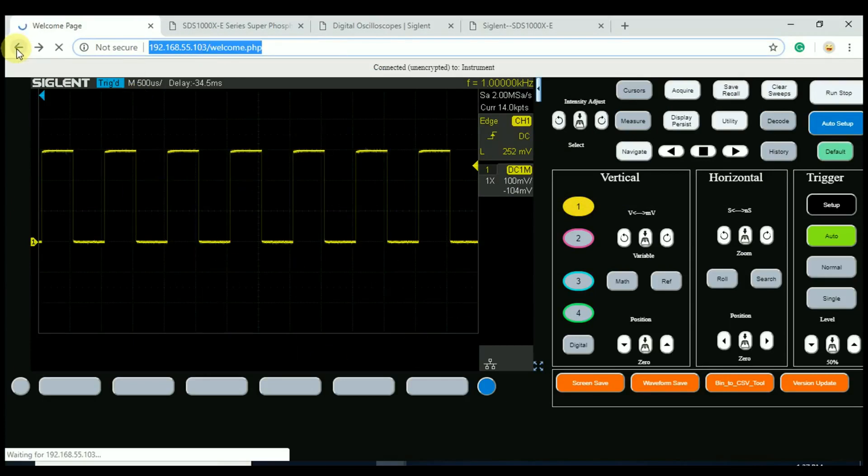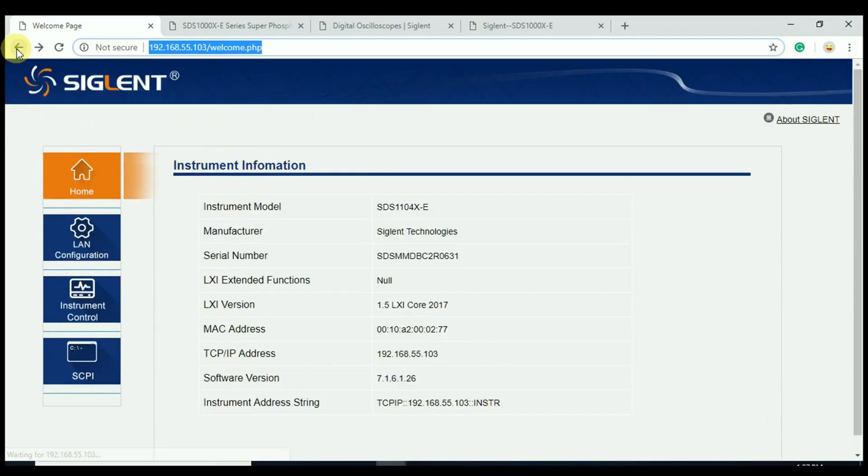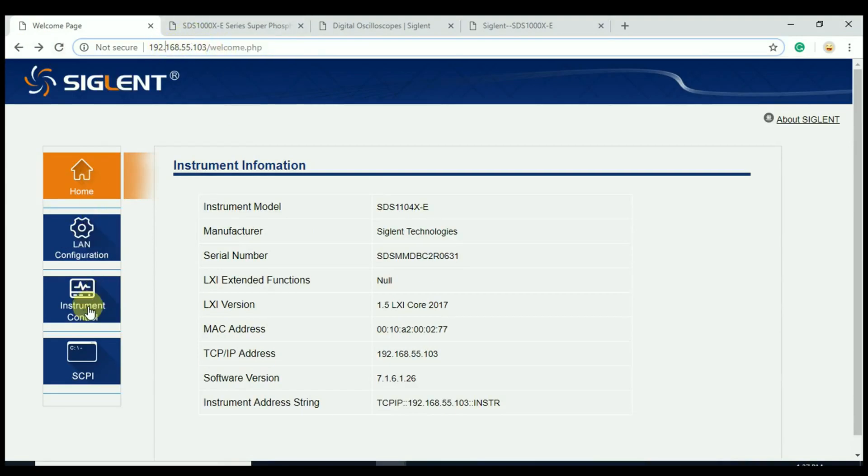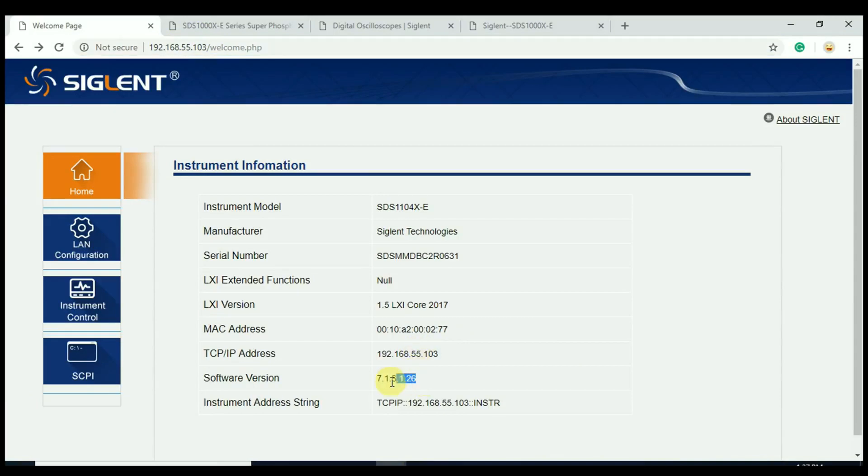So just go back arrow to the welcome page, type in the IP address up here, hit enter, and we come up with the home screen here. We're going to see the latest software revision. We can hit instrument control. That's going to open up here.